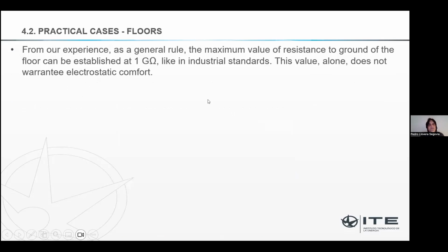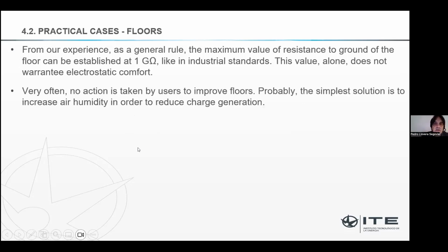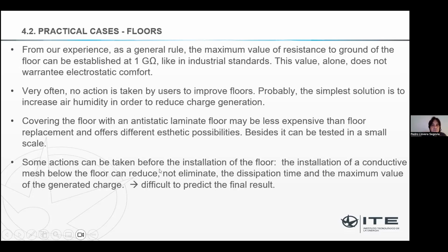From our experience, in general, the rule of 1 gigaohm, 10 to the 9 ohms, like in the industrial standard, is okay. It has also been taken in this new standard coming, but it alone does not warrant electrostatic comfort for floors. It depends also on the interaction with people. That's a very, very well-known problem with electrostatics. Probably the simple solution is to improve air humidity in order to reduce charge generation. Anti-static laminate floors, or some action can be taken before the installation of the floor. In one case with a marble floor, they put a conductive mesh below, but it was difficult to predict the final result. I think at the end it works, but it's a risky operation if you cannot make some tests before installing the floor.